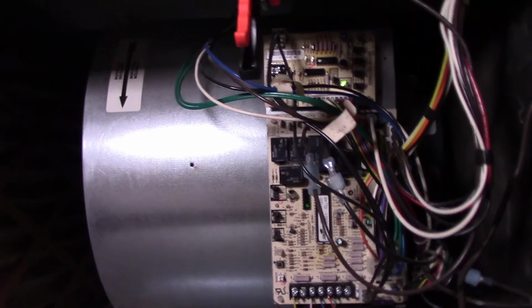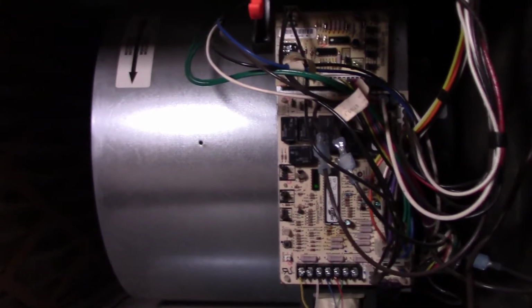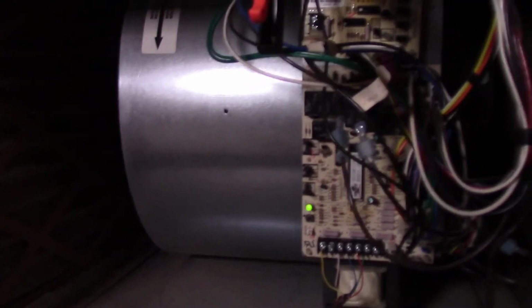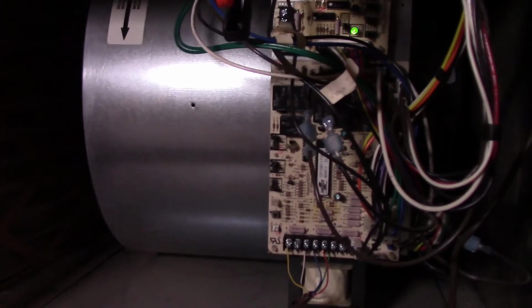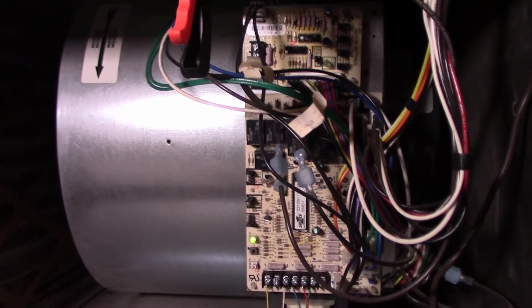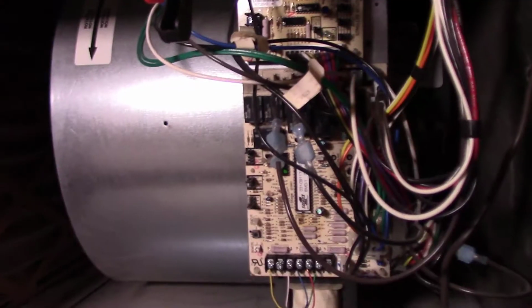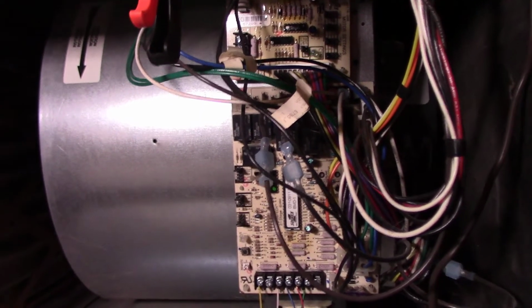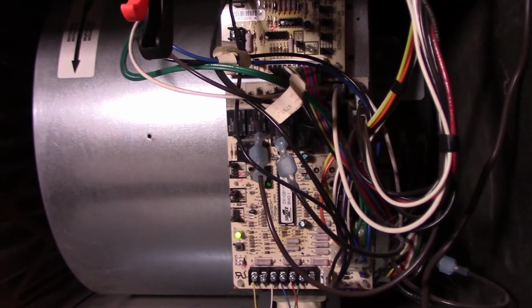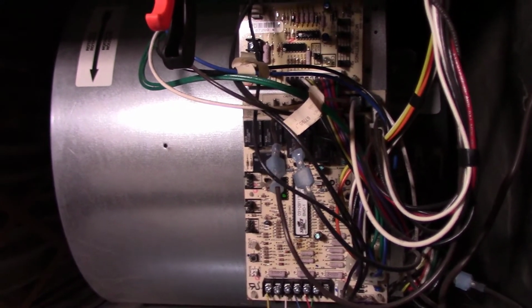Okay, now that we've got to this point, we have flame, we have inducer draft, we have all that stuff. But what happens if the last part of the process, the main blower motor, you don't hear that starting up? Well, the most common problem there is the blower motor could be bad. Usually what you'll start hearing is whining or squealing, like the bearings are going out. The other thing that could be out before you replace the whole blower motor is the run capacitor on the blower motor.